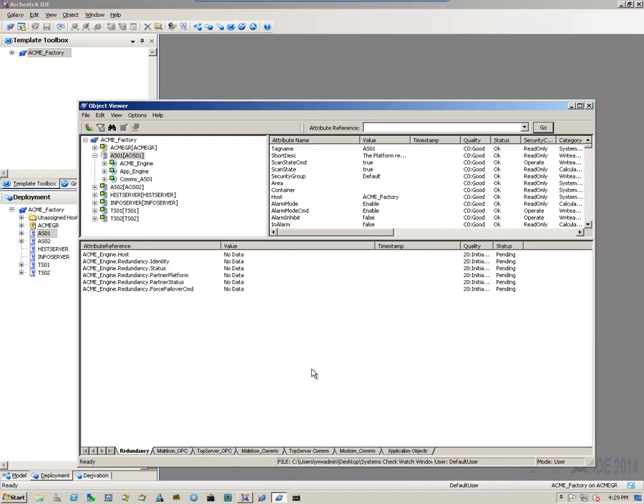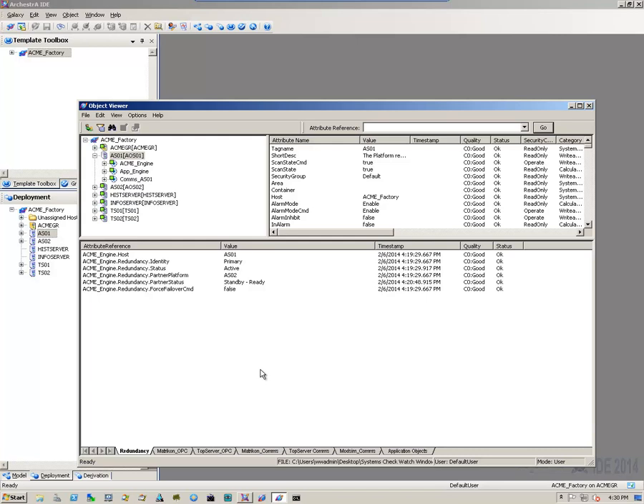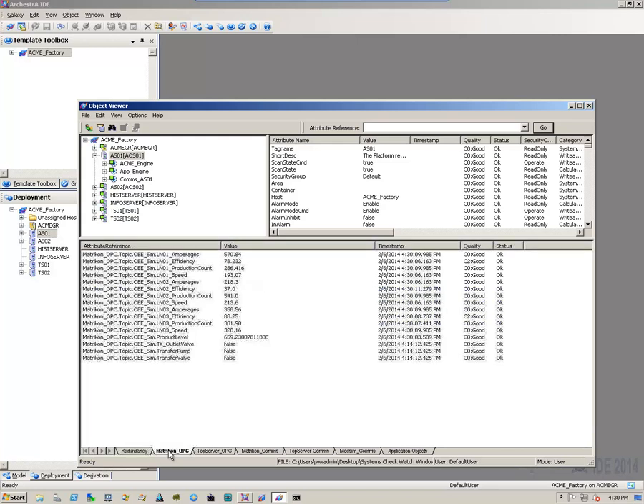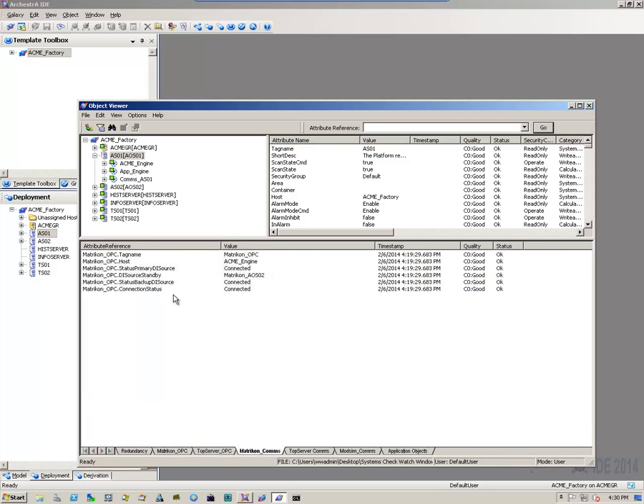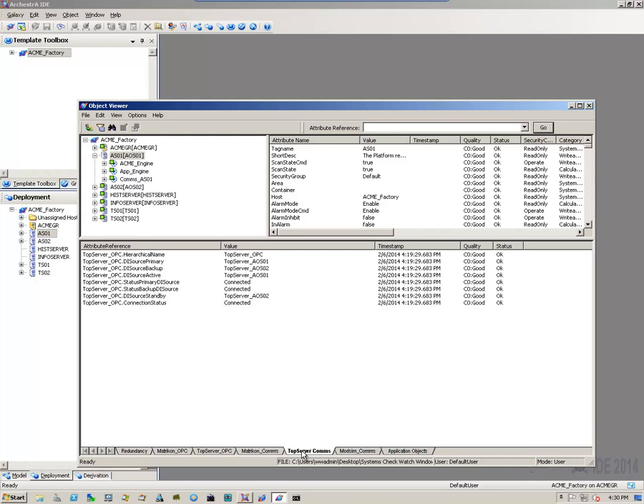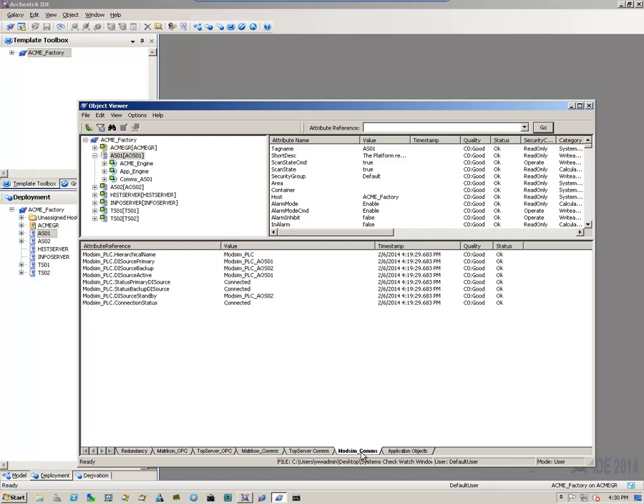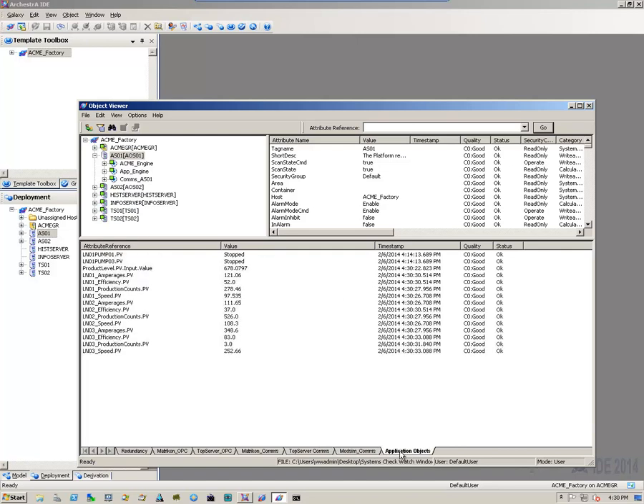And so I open up my watch windows that I previously saved, and from here I can check on the redundancy status. I can see that both my systems, my primary and my standby system, are online, and my standby is standby ready. I can check to see if I have communications coming into the galaxy. I can check the status of my IO to make sure that I'm connected to my OPC servers in this case. And I can see the status of certain objects within my galaxy itself.